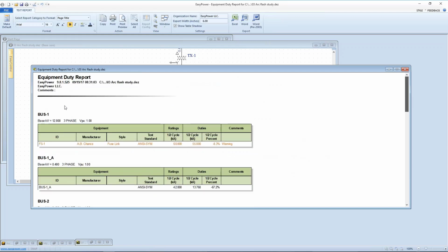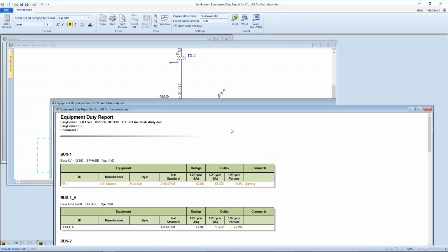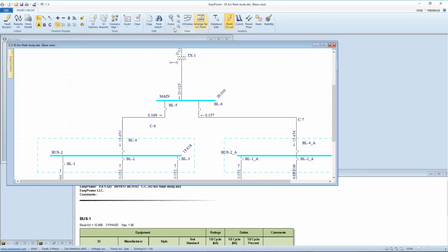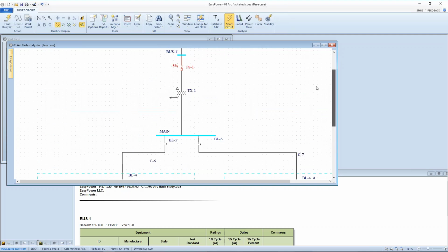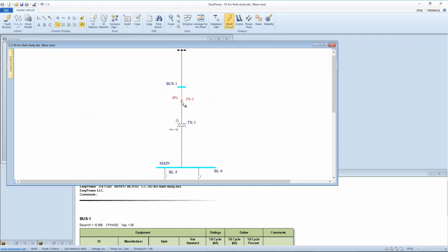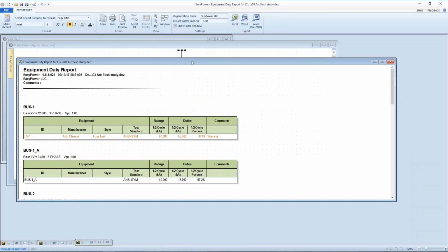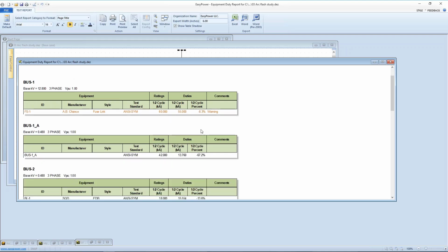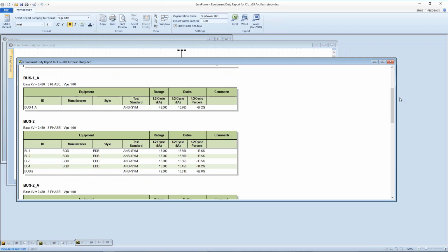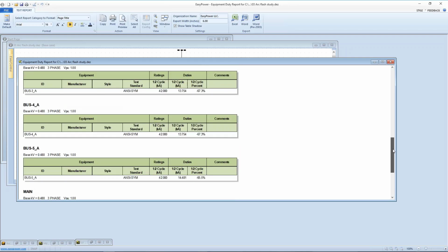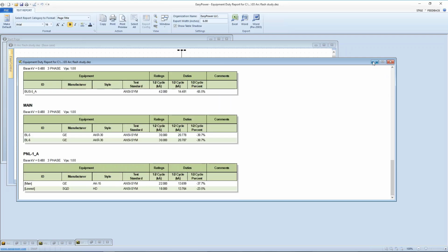We'll notice here on my equipment duty report that, and I can actually do this on the one-line diagram, in short circuit, I have an icon here that shows me equipment duty. I don't show anything flagged on the lower buses, but when I get up here to my fuse, it says I have a negative 8%. When I look at the details on that, that says, well, my fuse itself was rated for 60,000 amps. We're actually seeing 55,000 amps as a worst case. So it's within 10%, which is where I set my warning level of being non-compliant. So that's not an error at this point, it's just a warning. Whereas all the rest of my protective devices are not exceeding the worst case fault that the system will see at that point.